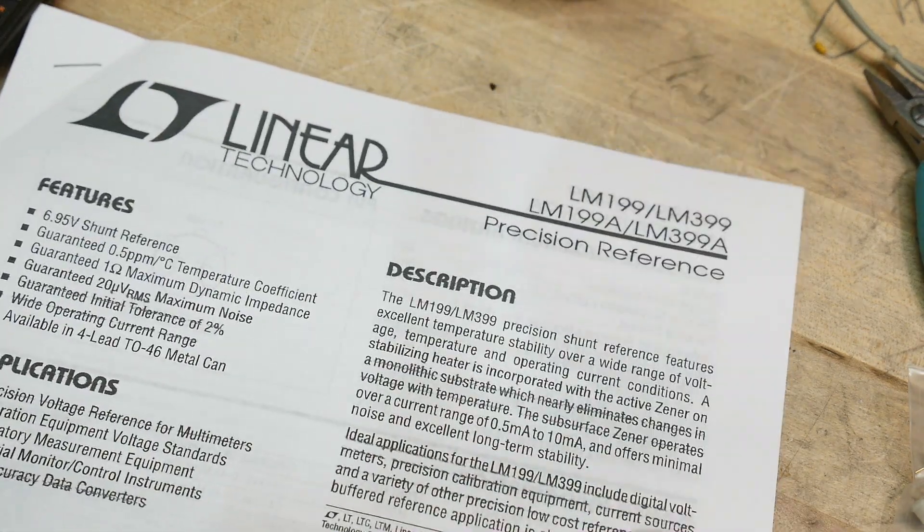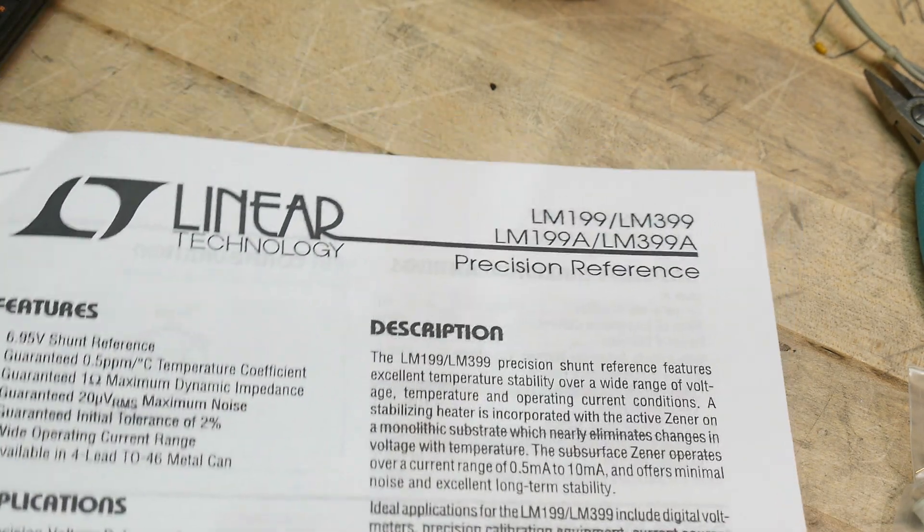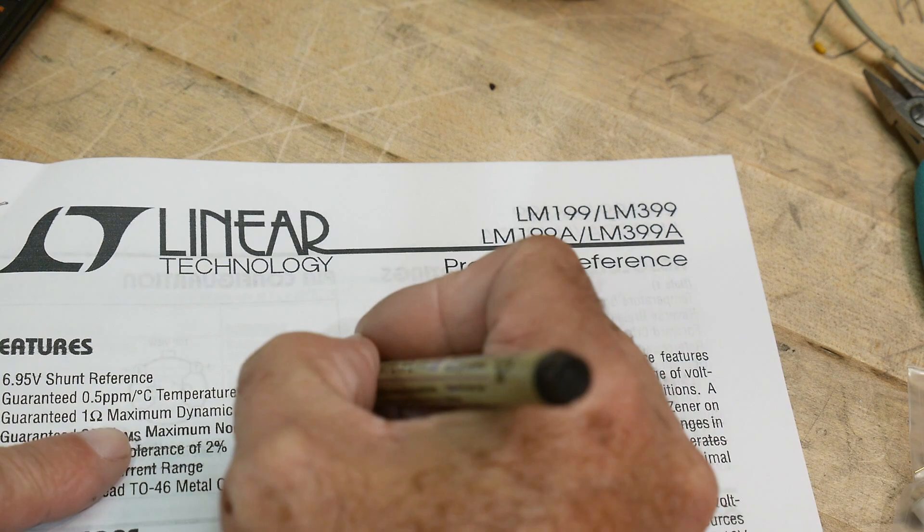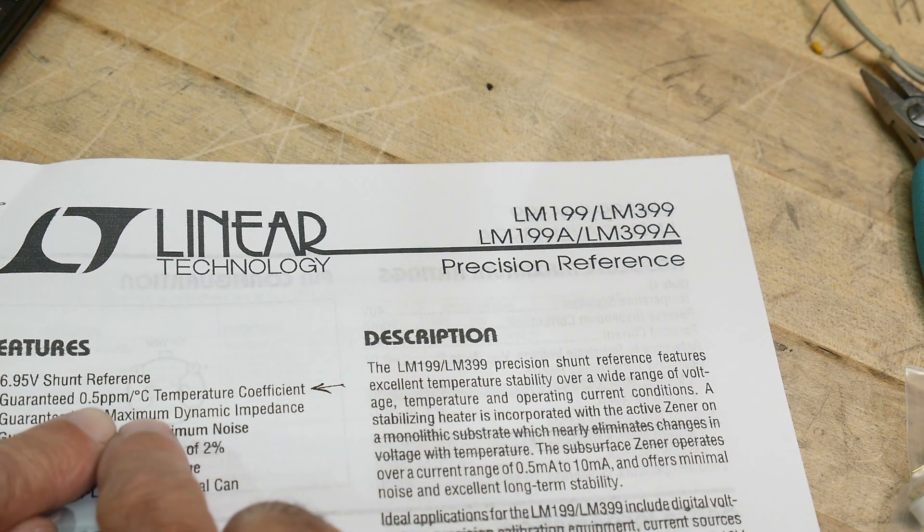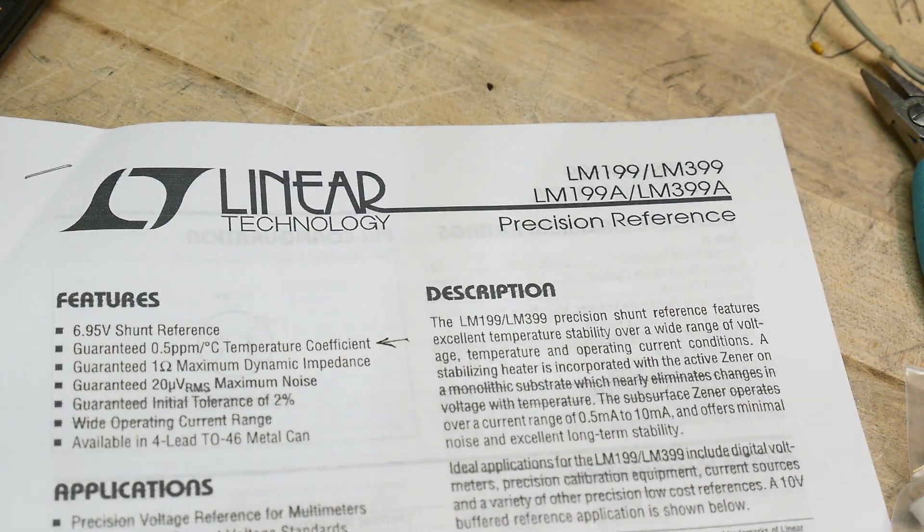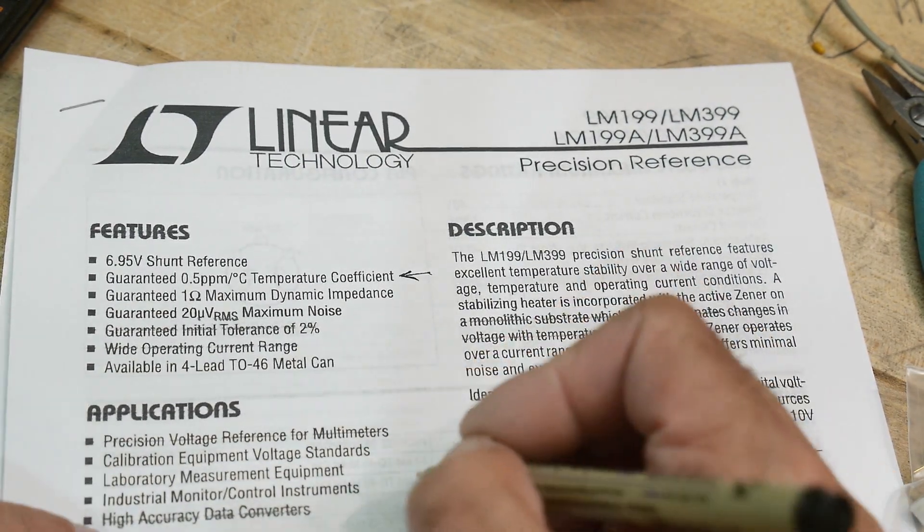Before we turn one on, I want to talk about the specification that you really care about. It's this one right here: guaranteed 0.5 ppm per degree C temperature coefficient. Let's talk about what that means. A lot of people don't understand ppm. PPM stands for parts per million.